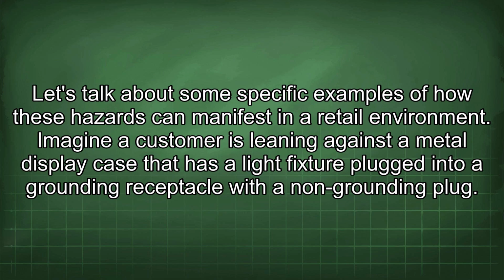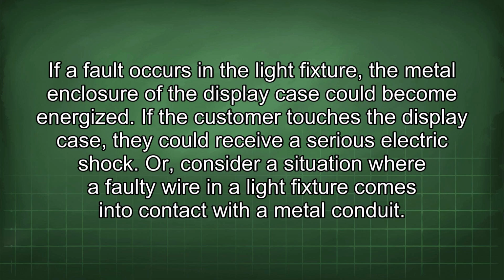Let's talk about some specific examples of how these hazards can manifest in a retail environment. Imagine a customer is leaning against a metal display case that has a light fixture plugged into a grounding receptacle with a non-grounding plug. If a fault occurs in the light fixture, the metal enclosure of the display case could become energized. If the customer touches the display case, they could receive a serious electric shock.